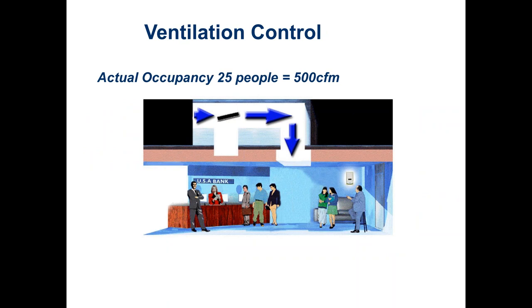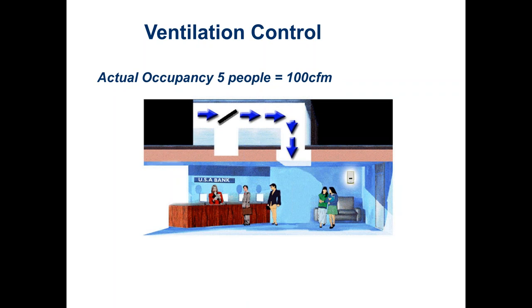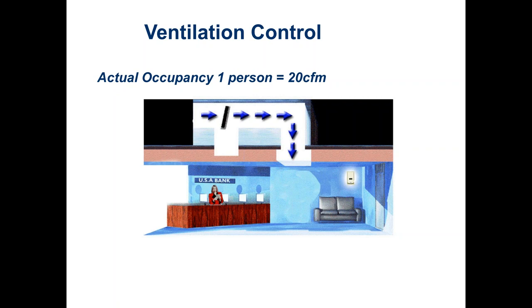Using that same bank example with a CO2 sensor on the wall: with all 25 people present, we'd bring in the code-required 500 CFM. With only five people, we'd modulate the ventilation damper back down to about 100 CFM. With just one person, we'd throttle it back to 20 CFM. In practice, we'd probably never go that low because there are other reasons to have outside air — like pressurization control. So we'll have minimums in the system, but occupancy will be the driving factor.